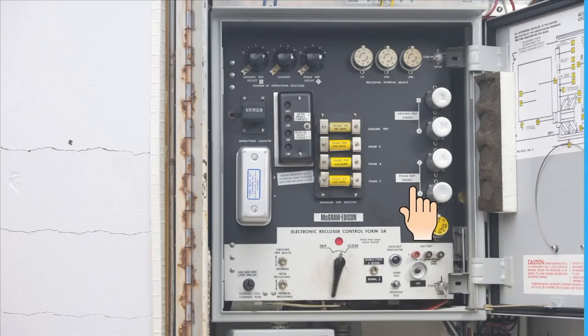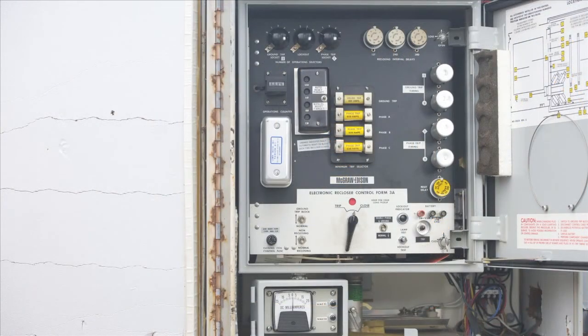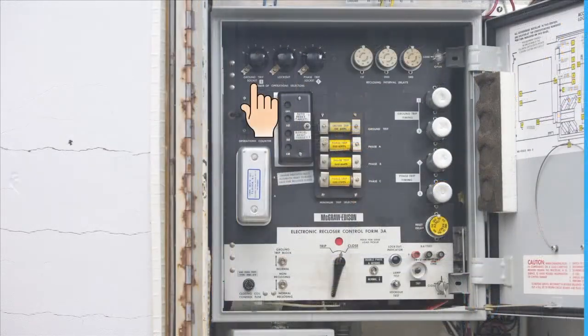Operation. Factory-calibrated timing plugs establish the time current characteristics for both phase and ground tripping. 2 sets of individual timing curves provide dual timing for both phase and ground. The line current conditions are continuously monitored by the 3 bushing-type current transformers in the recloser. Output from these transformers is fed to the trip network in the control, which includes the minimum trip resistors, isolation transformers, and rectifier circuits. If current remains above the minimum trip level, the tripping reclosing sequence of fast and delayed operations is repeated as programmed to lockout.